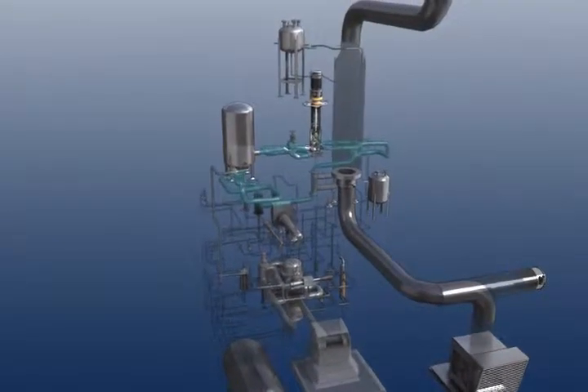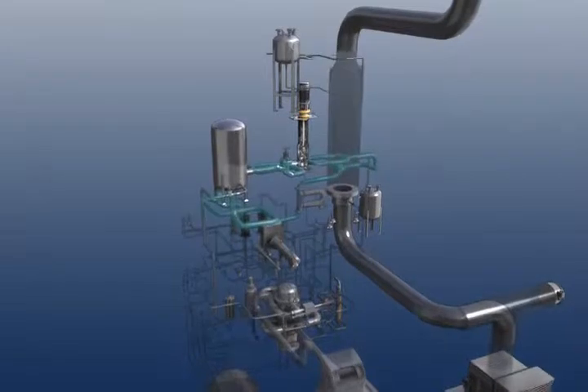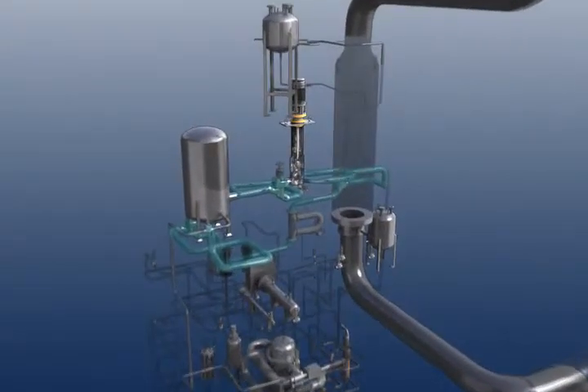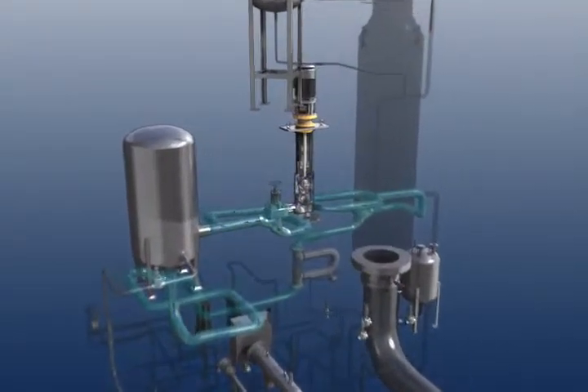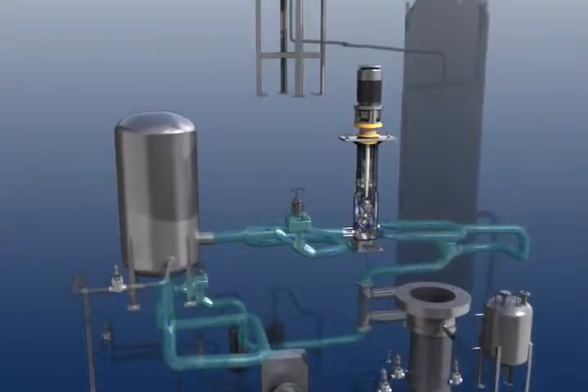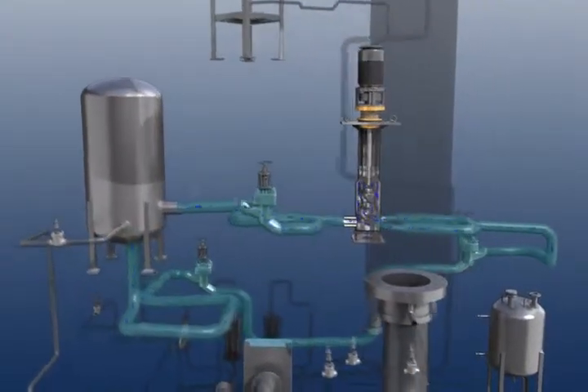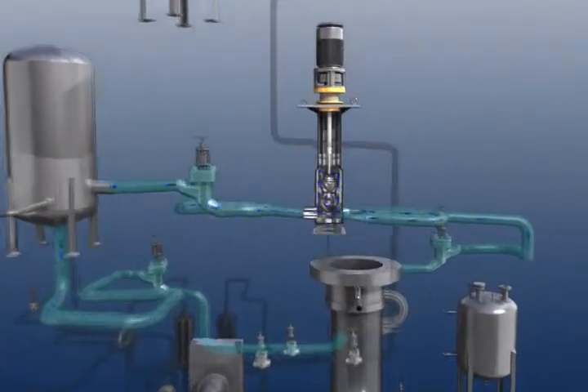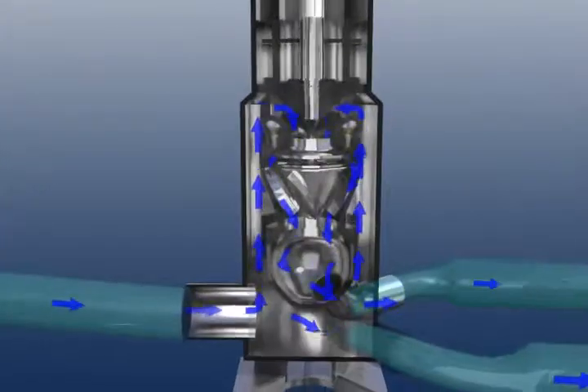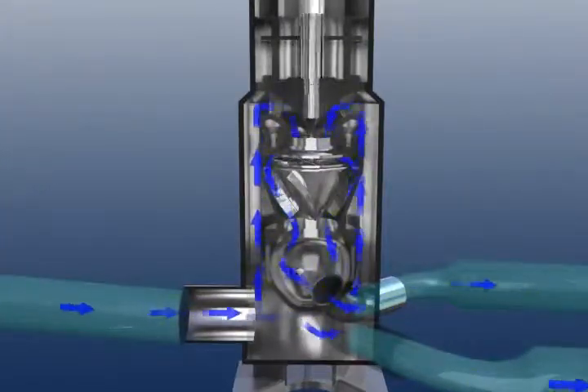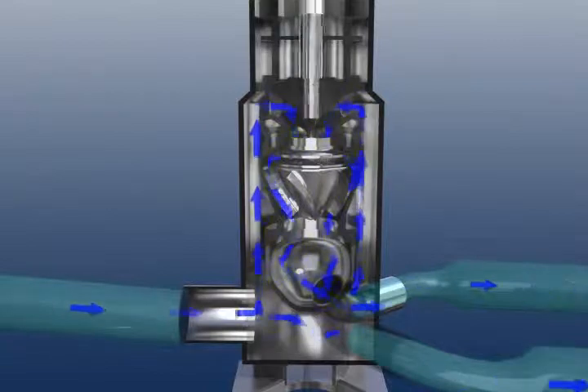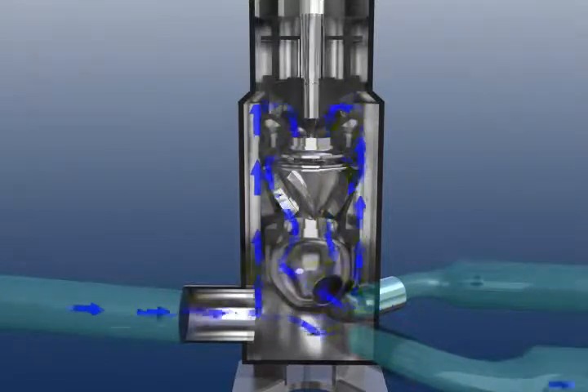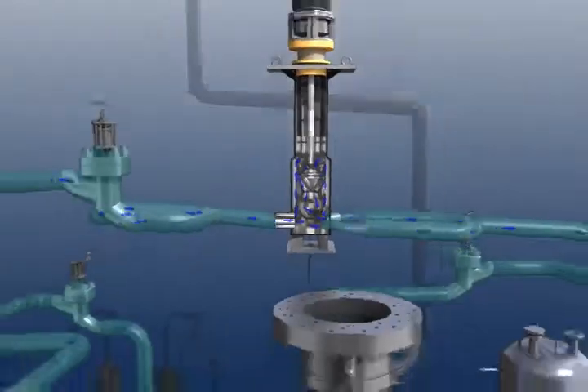The PHTS pump test loop consists of a reservoir, pipes, valves, and a vertical pump unit. This loop is equipped with various sensors for measuring flow rate, temperature, liquid sodium level, and so on. The main test loop is designed to simulate the transient operation mode using a flywheel as well as the normal operation mode.